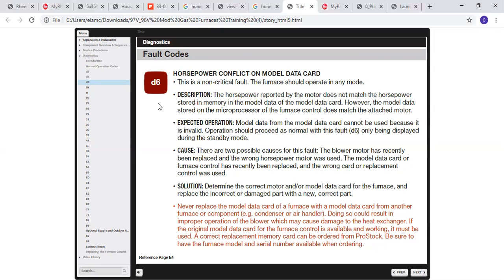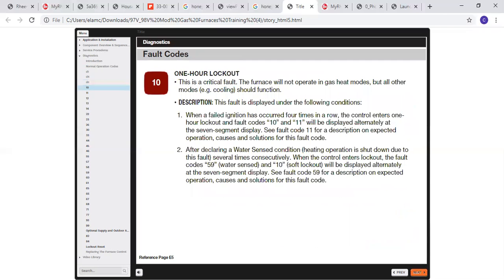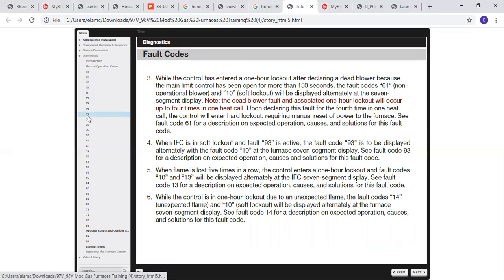If you do end up using a different card, you'll get a horsepower conflict on model data card. This is a non-critical fault. Two possible causes. The blower motor was recently replaced with the wrong horsepower, or the model data card or furnace control has been replaced and the wrong card was used. Solution, obviously determine if you have the correct motor and the proper card. Once again, because it's been tried more than a few times, never use another model data card from another furnace to substitute.